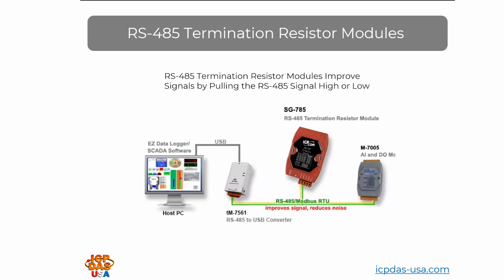We also have I-7510, which repeats the signal, which would make your RS-485 communication stronger and also communicate farther. So, RS-485 communication supports communication distances up to 4,000 feet, so you can extend that communication with a repeater like I-7510.